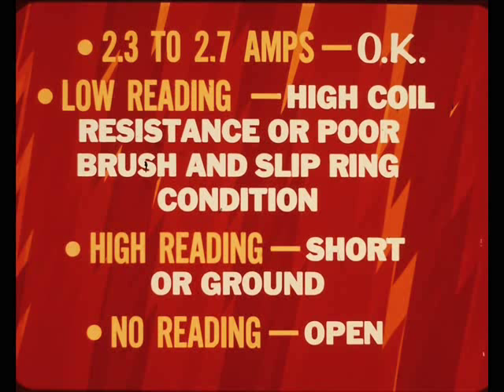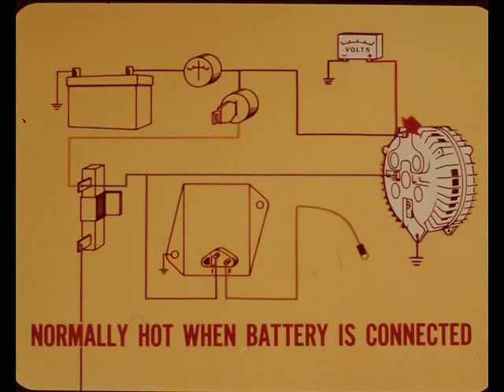A low reading points to high rotor coil resistance or poor brush and slip ring condition. A high reading usually means a short or a ground. No reading, an open in the rotor or field lead. If the rotor checks out okay, the next test point is at the alternator output terminal. This terminal is normally hot when the battery is connected, so you can check it for voltage without running the engine. No voltage at the terminal tells you that the charging circuit is open somewhere between the alternator and the battery.